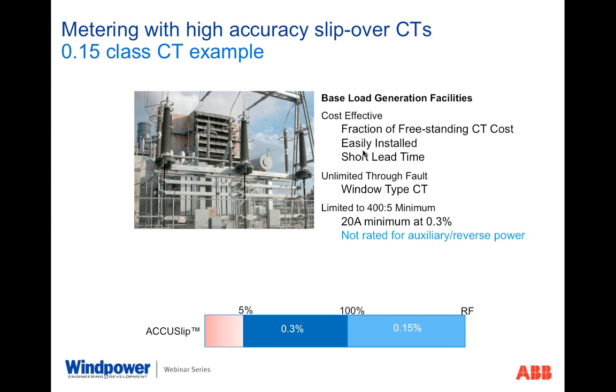The drawback of this, though, still relative to the wind farm developers, is that it's not accurate enough on the low end to be used in those applications. We can't use it for auxiliary reverse power needs. So in this application, even though it's excellent for baseload facilities and metering any current for 20 amps and up, it really doesn't satisfy the needs for the connectivity relative to the transmission grid operator. So they will push back on anything that does not provide accuracy below 5%.